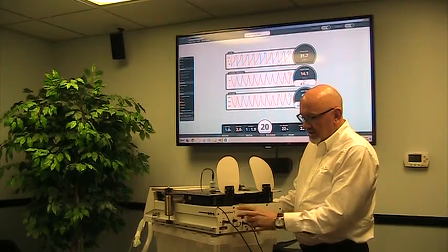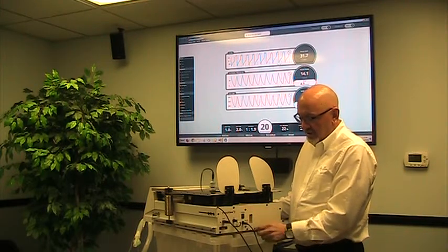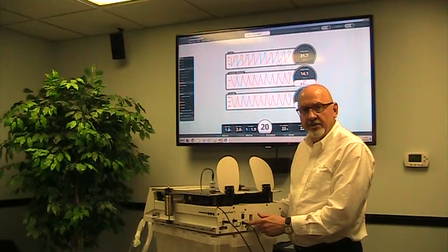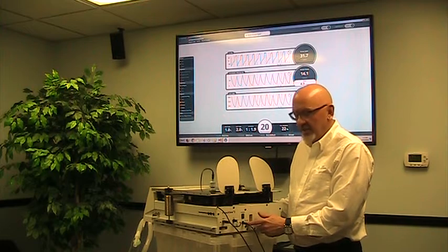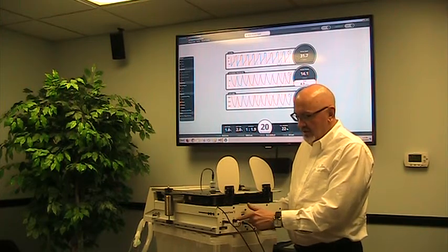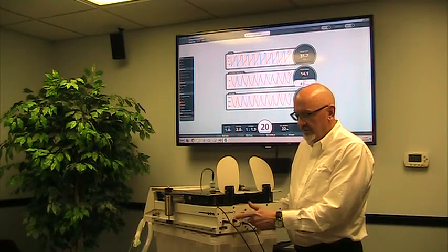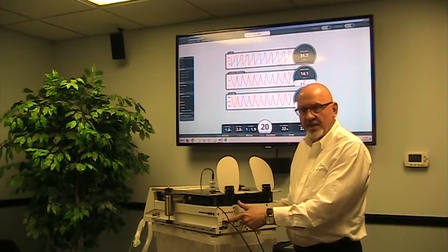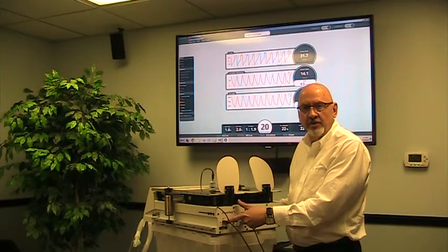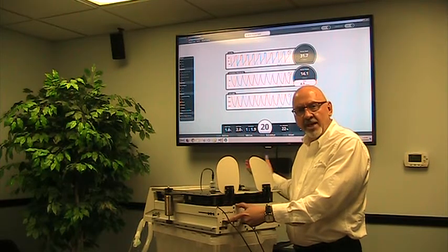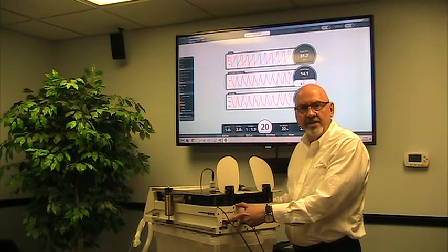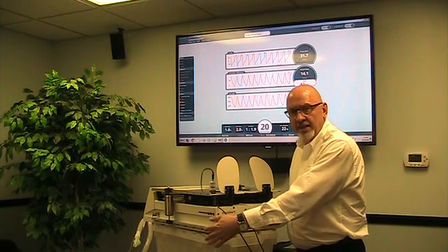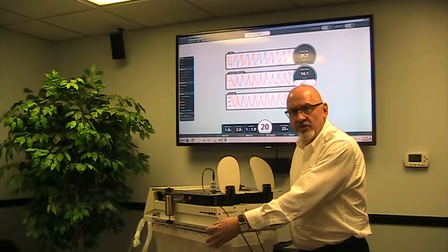These modules have three connections. There is a connection for the 12 volt DC power supply. There's a connection for your oxygen sensor and there's a connection for the USB cable which is going to be communicating with the PC where you're running the NuView software.